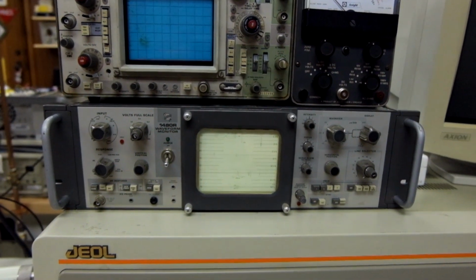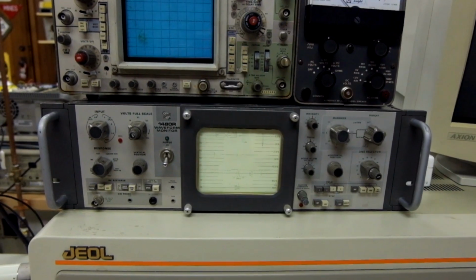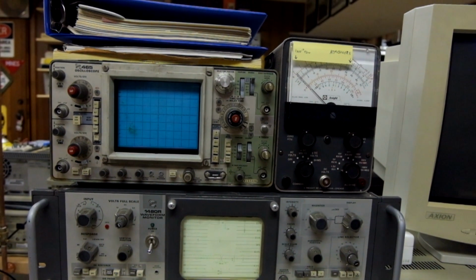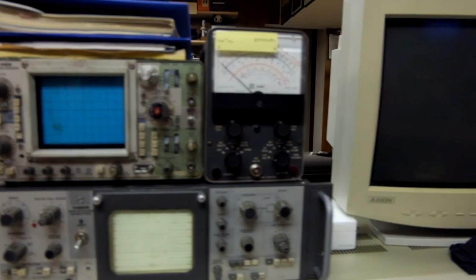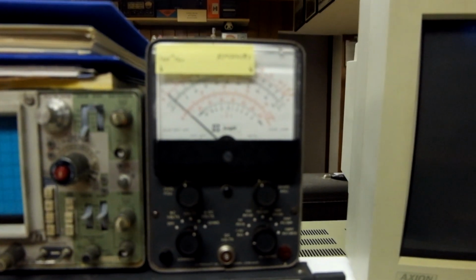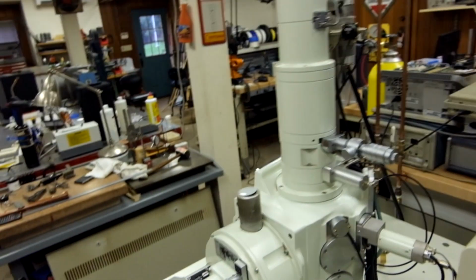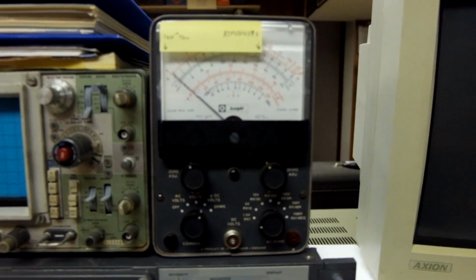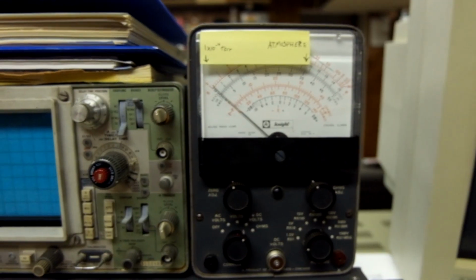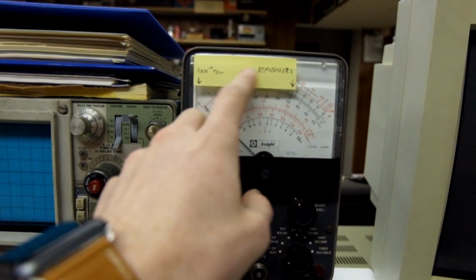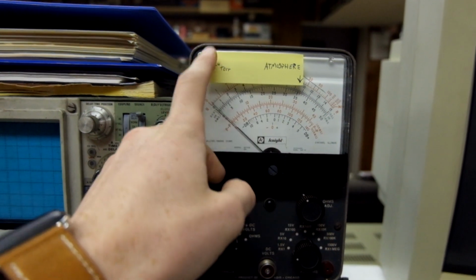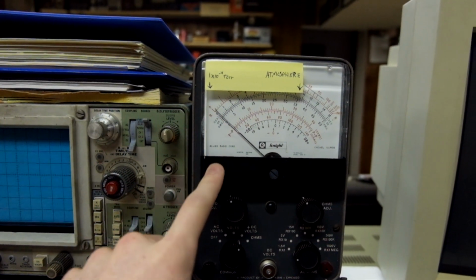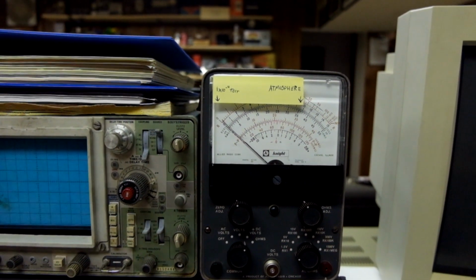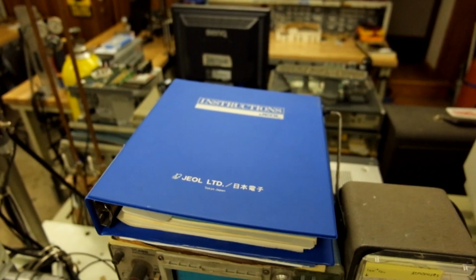On top of the console here, I have a Tektronix waveform monitor, so I can center the NTSC analog video. On the oscilloscope, I was playing around earlier with measuring the probe current, and this is my really high-tech vacuum meter. So this is wired in. The column over here has 3 Pirani gauges on it, so I tapped into one of them. It's not accurate, but I can get a quick visual on whether we're at atmosphere, pumped down, or somewhere in between. And pump down on this is about 1 × 10⁻⁴ torr, because this is a diffusion pump based machine. That's in the big manual, which I couldn't have got it working without.